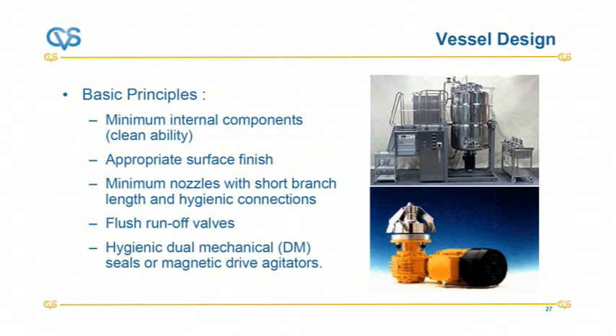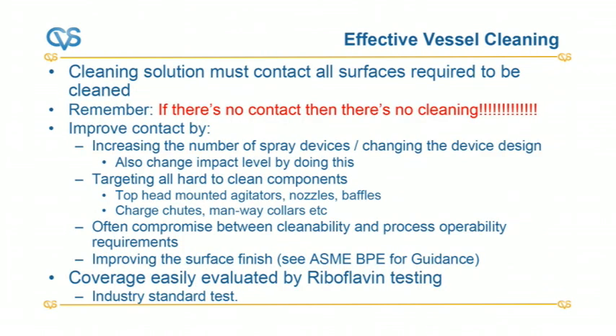Now, if we can get that right, we're minimising the challenge to the cleaning process. If we've got something full of crevices, full of internals, there's more and more areas for residues to build up. If we've got more portals, or a vessel that's got 10 spare portals we don't need, we're increasing our cleaning challenge. Now, the cleaning solution must contact all surfaces. Remember, if there's no contact, there's no cleaning.